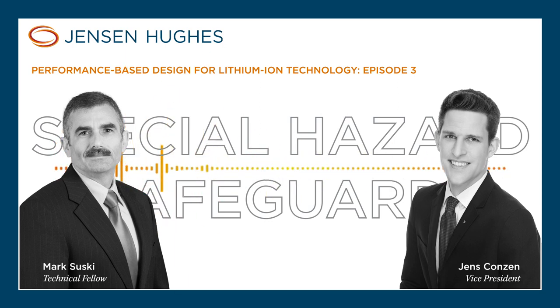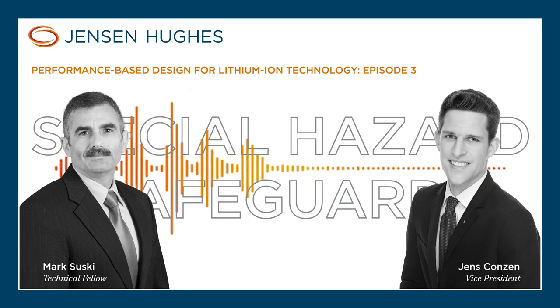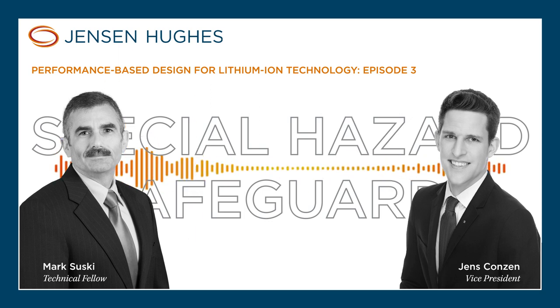By overlaying the smoke model, which gives us our available tenable environment time, with our egress analysis showing how long it takes people to get out of the building, we can show that by the time our fire smoke layer gets down to 6 feet, our people are all out and safe, and everybody's happy. We've done that in numerous places to help our clients get variances and get past that 400 feet travel distance.